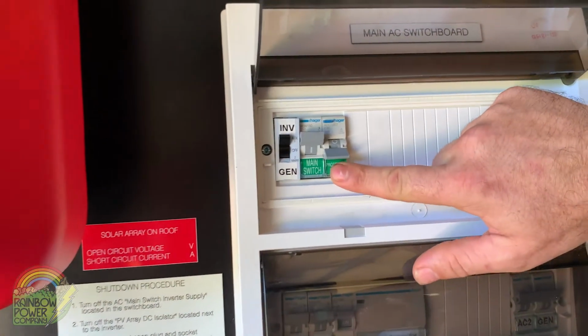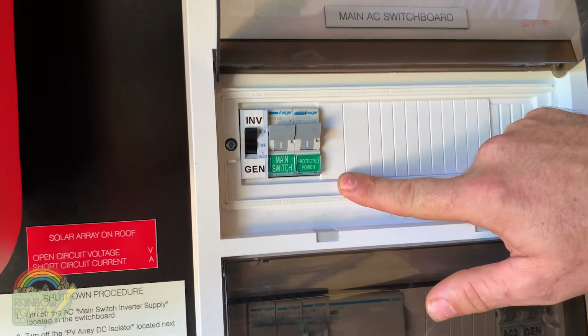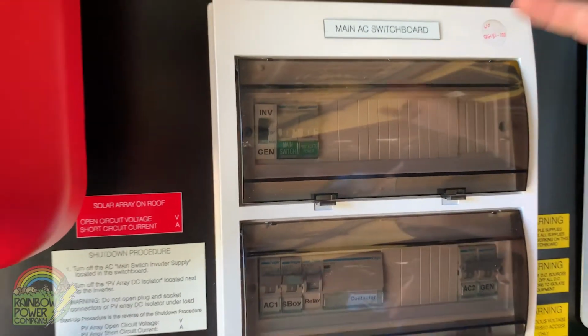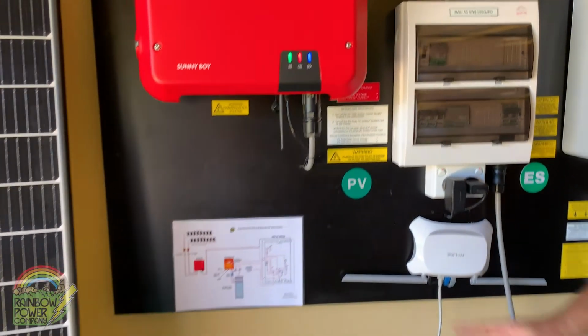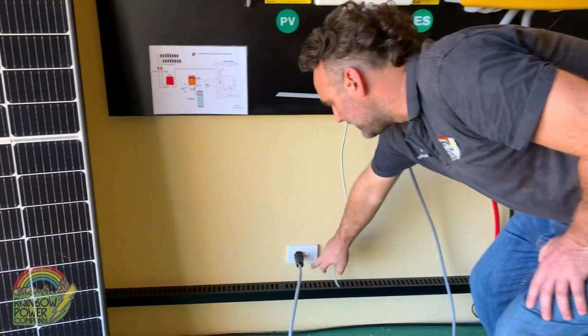Moving up, we now need to send the power out to the power points, so we turn our main switch on and our RCDs on. We now have power flowing out to our power points. Last but not least, we'll need to turn on all of the individual power points that we turned off during the shutdown.